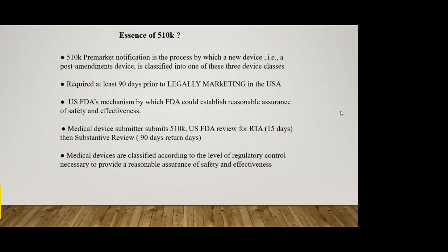So what's the essence of a 510K? When the FDA determines that a new device is substantially equivalent to a legally marketed predicate device, that device is classified into the same class and subject to the same regulations as the predicate device. So you pick a gizmo that's out there legally marketed, all of a sudden your device is the same as that device in terms of class, in terms of product code, in terms of the regulations that are involved in marketing here in the United States.